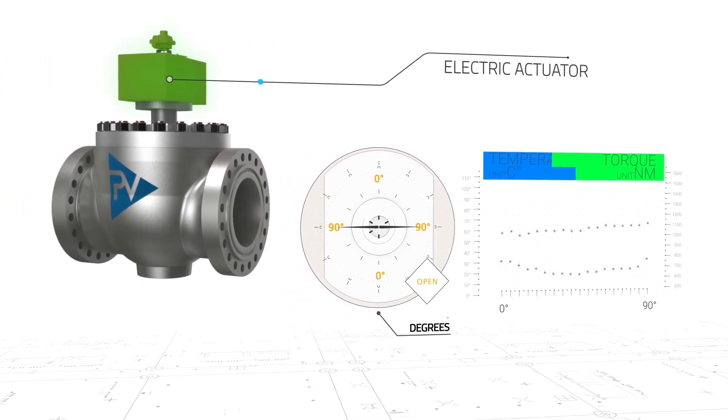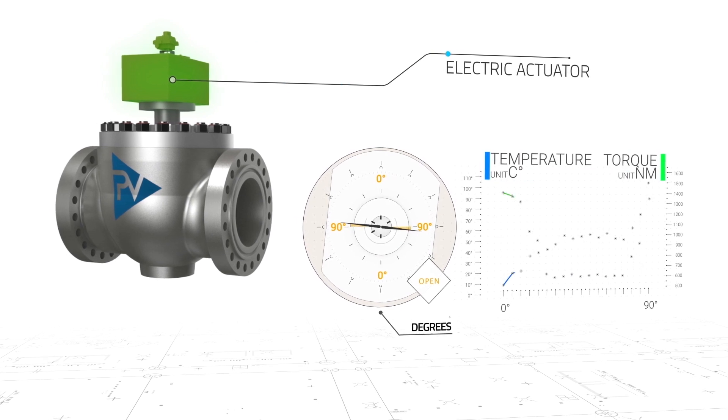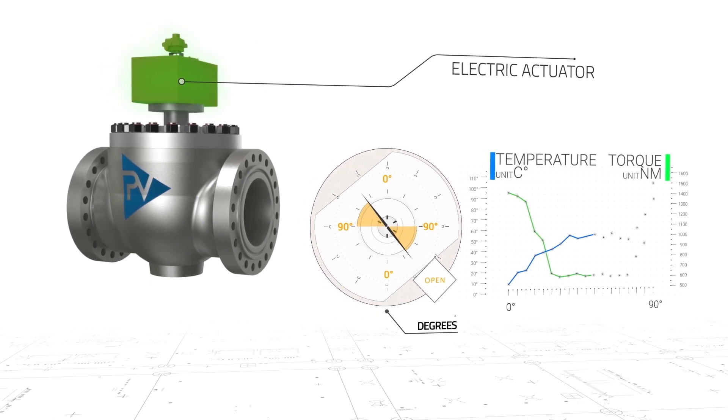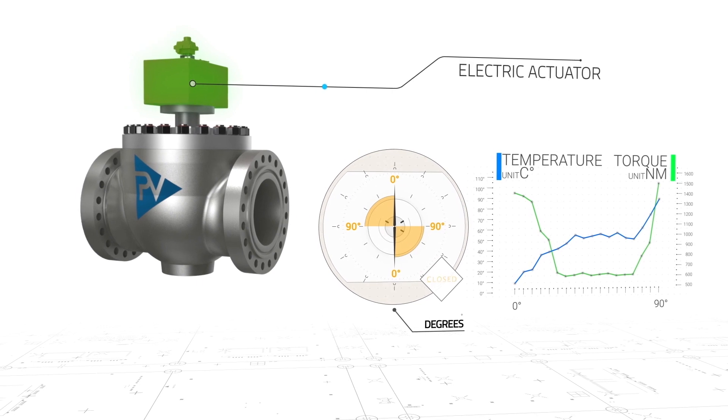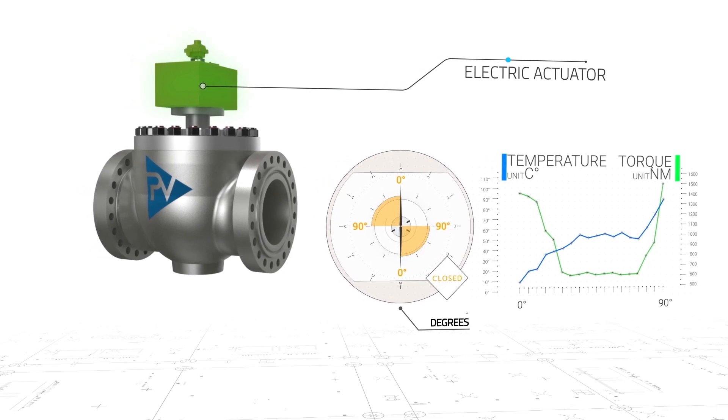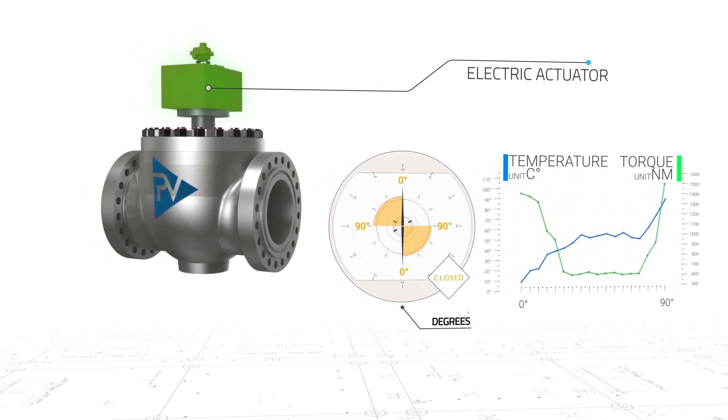Monitoring of torque on electric actuated valves. By monitoring the absorbed current, it is possible to evaluate the torque applied to operate the valve. The signal is connected to the data acquisition and transfer system.